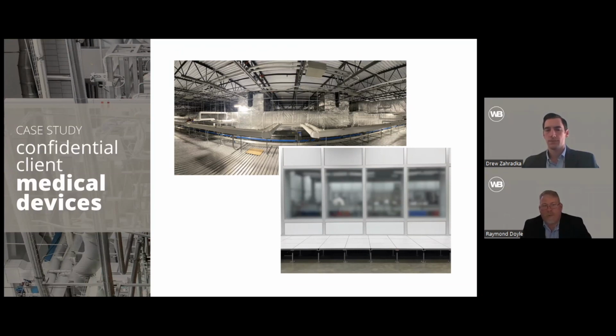So we ended up making sure that when the original science group said we want raised floor everywhere, we need unidirectional flow, as a good engineer, we challenged that question and said, for this classification, you really don't need it, based on a standard definition of that classification of clean room. And then we challenged it and walked through where they needed the clean room. We made sure that the spaces they needed to be clean, like again, back at the elevation of the space, you don't have to have the extra clean room classification if you don't need it, for example, at the floor. If it can be dirtier at the floor, you don't need the raised floor, completely unidirectional flow.